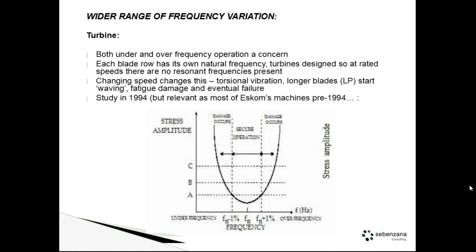The blades start flapping around and we get fatigue damage and eventual failure. If the blades go, you have a disaster on your turbine — this is not to be taken lightly. There was a study done in the 90s that affects industrial machines, most of which are pre-1994. It shows that as soon as you go more than 1% over or under frequency, you start getting into the potential to cause damage. Certainly at 2% — which is fine for the generator, which is rated for 2% — the turbine starts to become problematic. I'm not sure how much the turbine guys are involved in these grid code discussions.